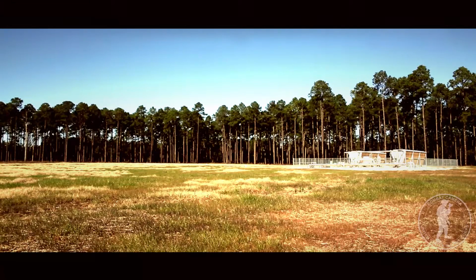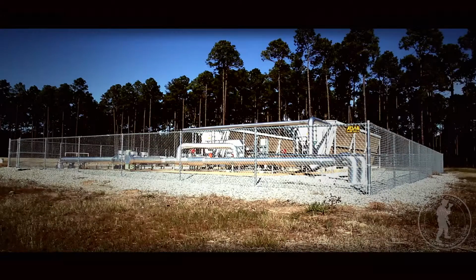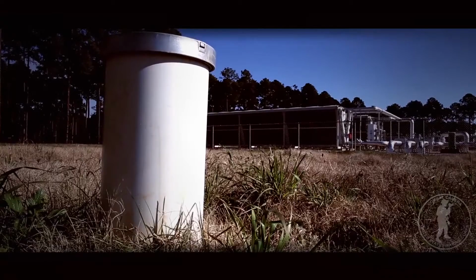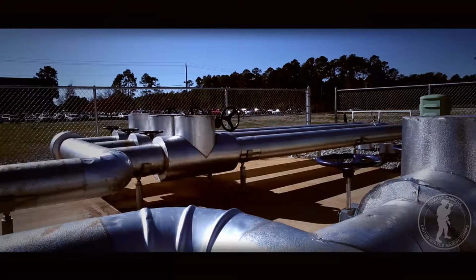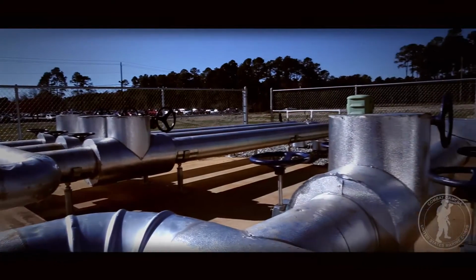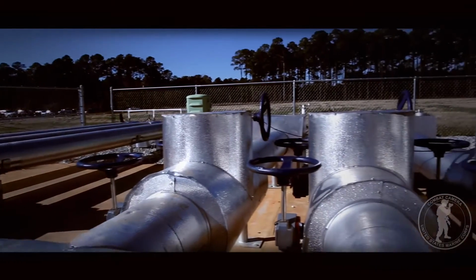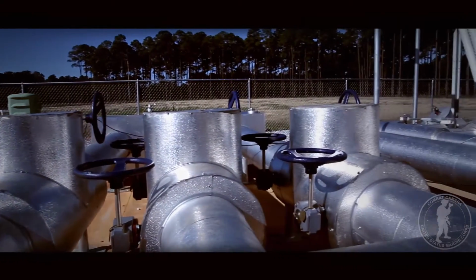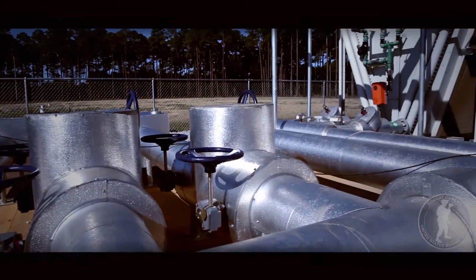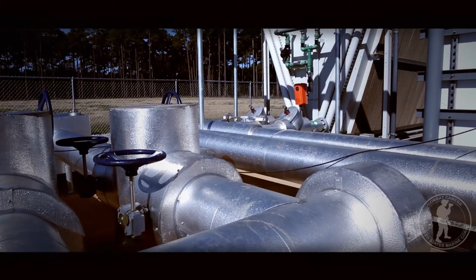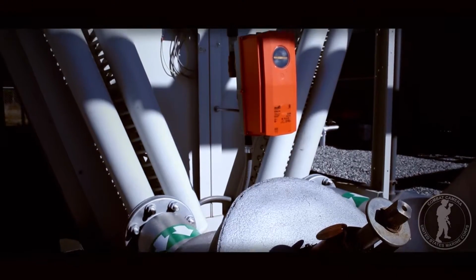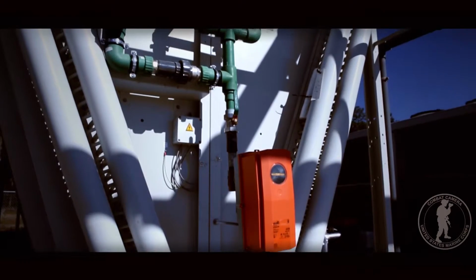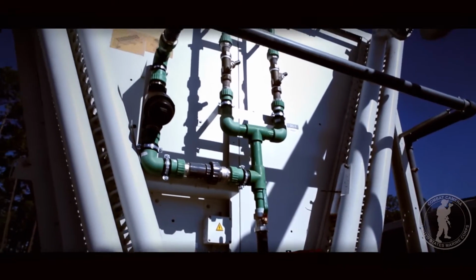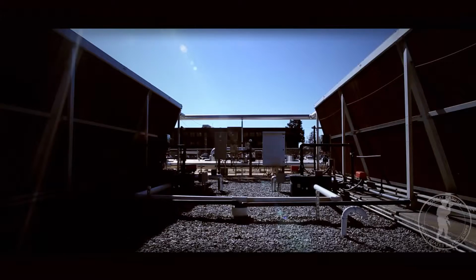The 3-acre borehole thermal energy storage well field includes 306 wells that are each 210 feet deep, located in concentric circles to regulate underground water storage temperature in the karst limestone aquifer. The adiabatic dry coolers are used to balance the well field storage, resulting in an extended life of the field to beyond 30 years. A conventional unregulated well field would be spent or overheated within 7 years due to the South Georgia climate.